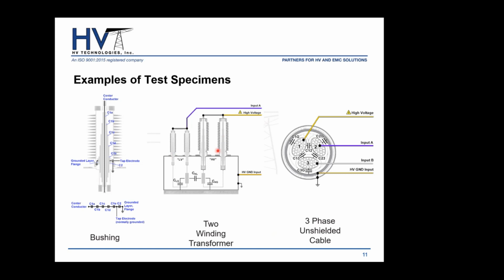And so the capacitances that we model in a two-winding transformer exist between your high voltage and your low voltage winding, and also from your high voltage winding to the ground and your low voltage winding to the ground. So for a two-winding transformer, essentially you're going to be making 3 measurements to test your capacitance and dissipation factor. For other specimens such as cables, you have more capacitances that are modeled. For example, you'll have your intercable capacitance from one cable to another. In this case, for cable 1 to 2, from 2 to 3, and from 3 to 1. So you have 3 measurements that you will do for in this case a 3-phase cable to shield.